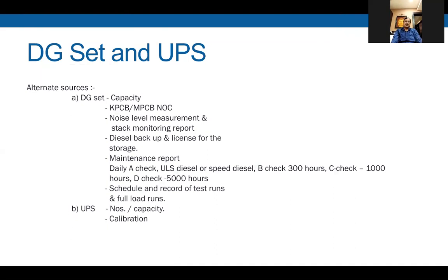Normally, you should not use any other diesel apart from ULS diesel or high speed diesel, because that spoils the generator completely. Then you have preventive maintenance requirements for the DG sets. For example, daily there should be an A check. Then at 300 hours there should be a B check. C check is required at 1000 hours and D check is required at 5000 hours. This has its own components. For example, B check will involve battery checking, then it involves your motors, etc.